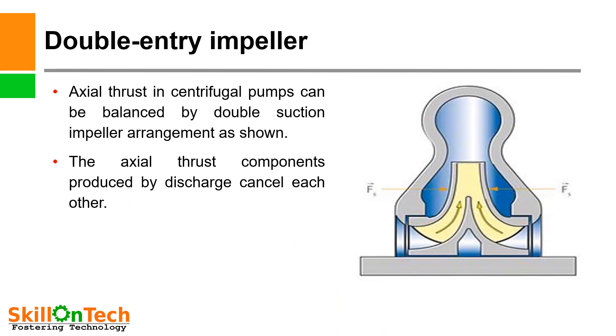Double entry impeller: You can see a picture of a pump impeller where the entry of suction is from both sides of the pump — from both directions. The pressure of the impeller shrouds on both sides will remain the same, so axial thrust components produced by discharge cancel each other and axial thrust is nullified. Double entry impellers are therefore a suitable measure to balance axial thrust in centrifugal pumps.